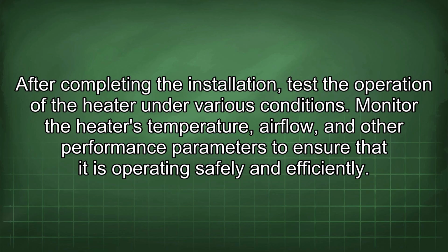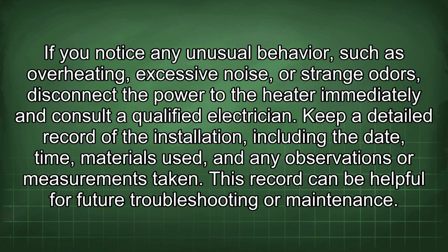After completing the installation, test the operation of the heater under various conditions. Monitor the heater's temperature, airflow, and other performance parameters to ensure that it is operating safely and efficiently. If you notice any unusual behavior, such as overheating, excessive noise, or strange odors, disconnect the power to the heater immediately and consult a qualified electrician. Keep a detailed record of the installation, including the date, time, materials used, and any observations or measurements taken. This record can be helpful for future troubleshooting or maintenance.